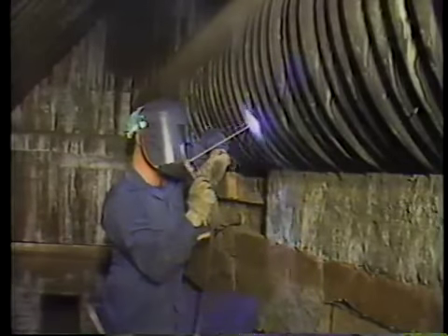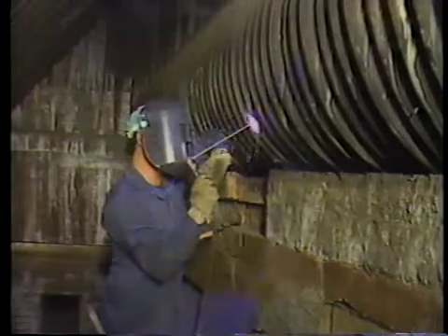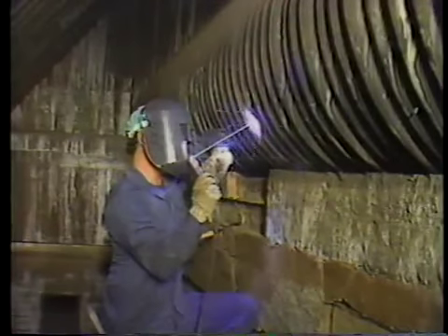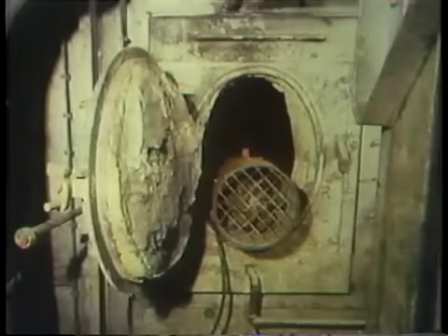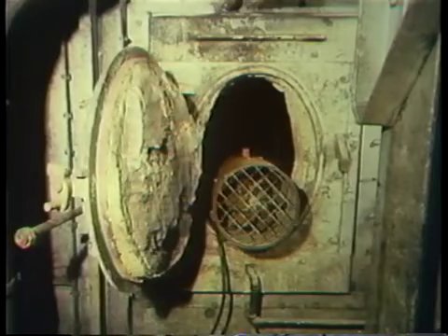There are several precautions that must be taken to protect against hazards caused by welding. First, the welder and his helper must be protected from the electric arc's intense light by welding shields. These shields have special glass lenses that filter this light to keep it from damaging the eyes. Second, the area where the welding is done must be well ventilated because of the harmful fumes produced by welding. In a confined area, it may be necessary to set up a portable fan to get adequate ventilation.